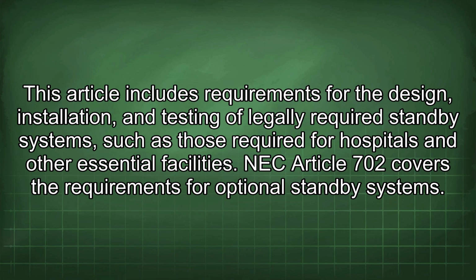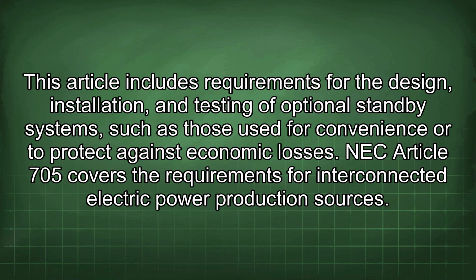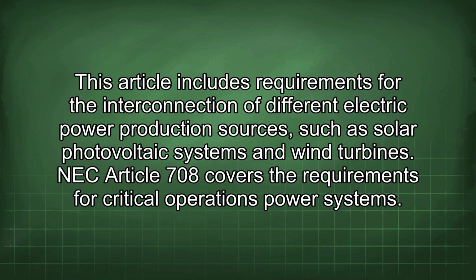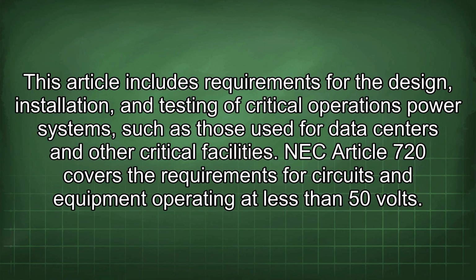NEC Article 702 covers the requirements for optional standby systems. This article includes requirements for the design, installation, and testing of optional standby systems, such as those used for convenience or to protect against economic losses. NEC Article 705 covers the requirements for interconnected electric power production sources. This article includes requirements for the interconnection of different electric power production sources, such as solar photovoltaic systems and wind turbines. NEC Article 708 covers the requirements for critical operations power systems. This article includes requirements for the design, installation, and testing of critical operations power systems, such as those used for data centers and other critical facilities.